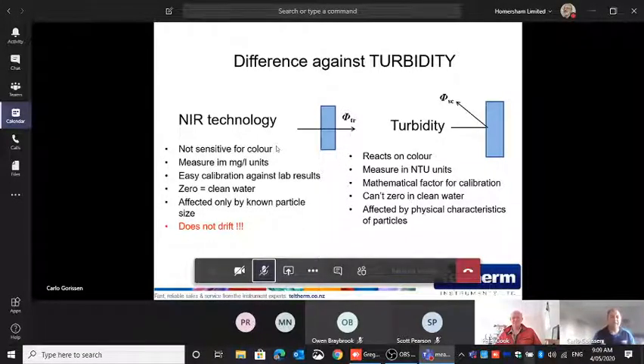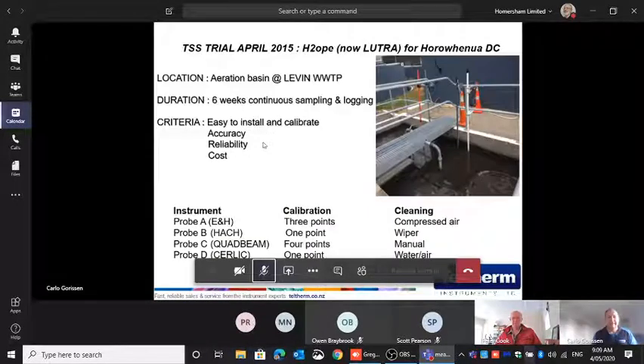It's only affected by particle size for us, not the physical characteristics of the particles. Of course, if you do scattering, if you got a round particle or a square or a triangle, it changes it. And the main advantage against turbidity is our sensors do not drift. So basically, once we install them and you do a calibration, you don't really need to touch them anymore, calibration-wise. People still trial it and test it. Now, of course, when we told everybody that, nobody believed us.